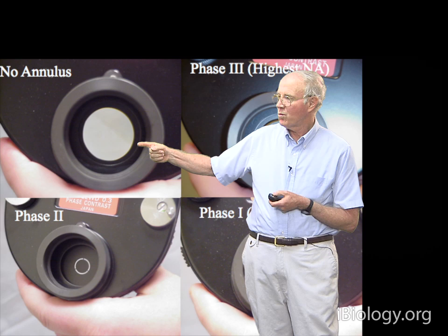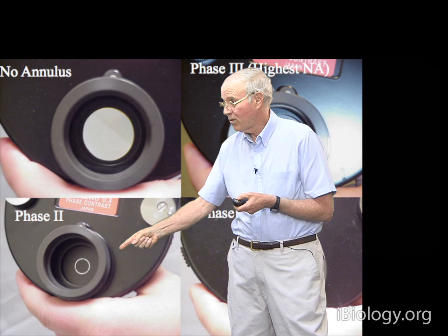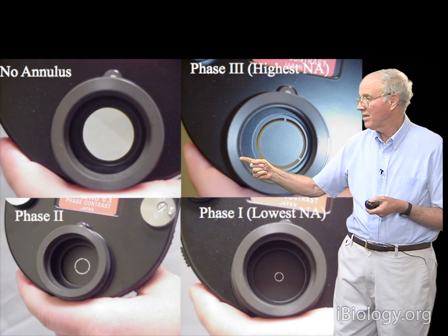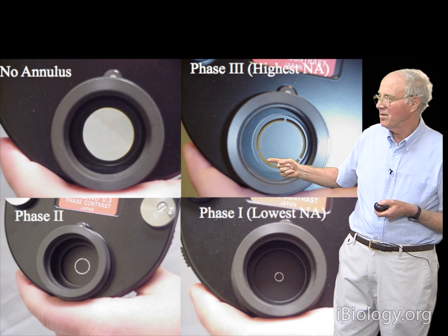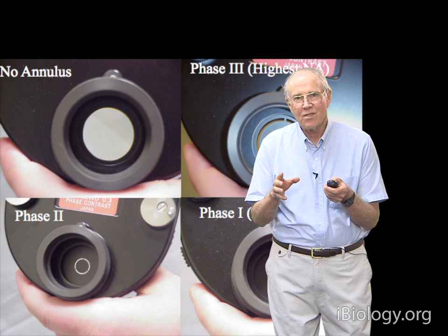Here's an inverted microscope used often for tissue culture microinjection. There's a holder for a needle for microinjecting tissue culture cells, and we observe those cells using phase contrast with a long working distance condenser lens. At the front focal plane of the condenser lens is a turret that can be rotated and has openings for three different phase annuli as well as one condenser diaphragm for full bright field illumination. The screws on the microscope are used to center the condenser lens for Köhler illumination, and Allen wrench screws are used to center each of the annuli inside the turret.